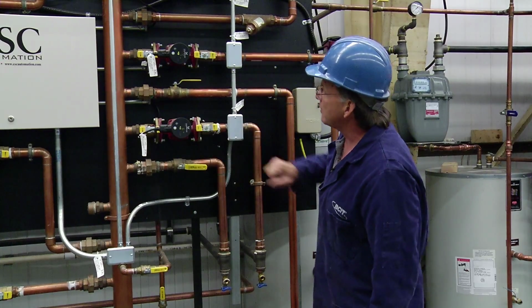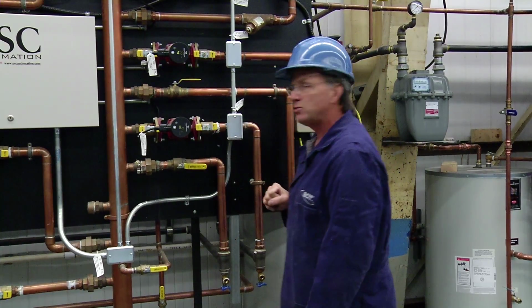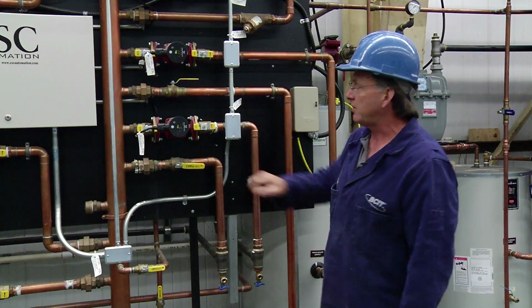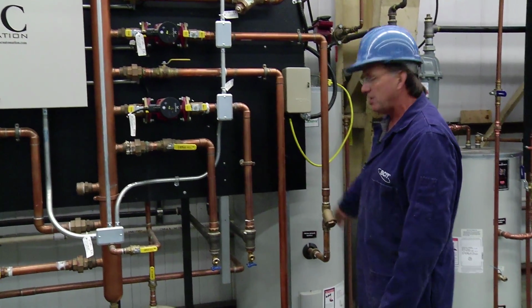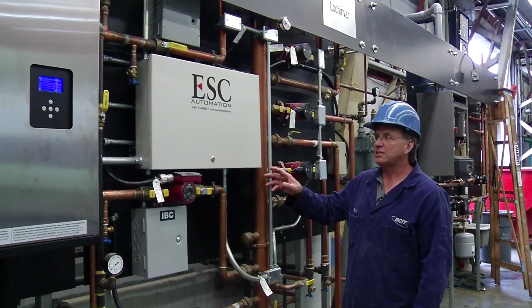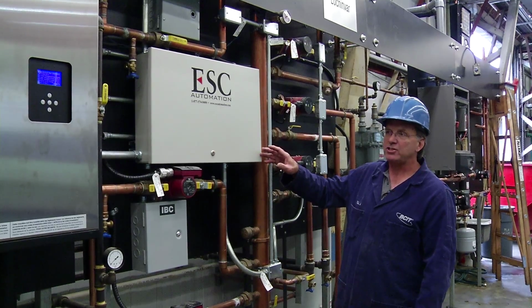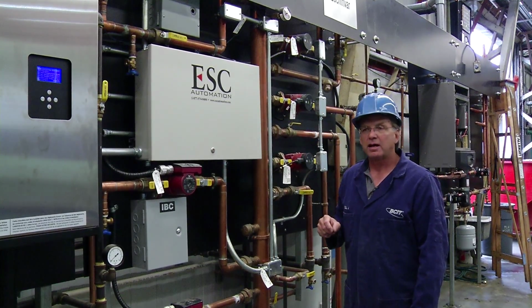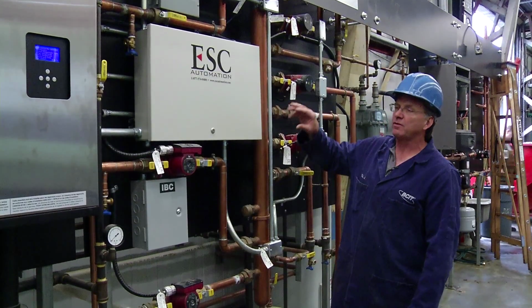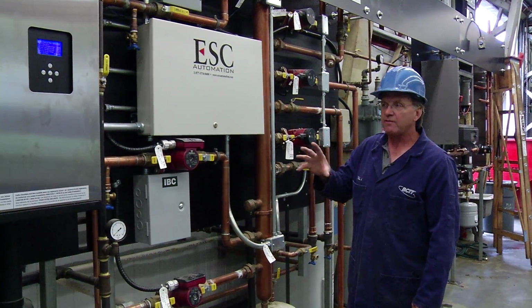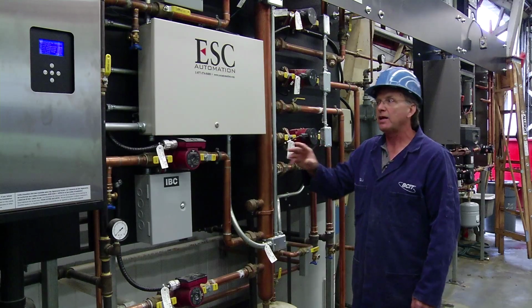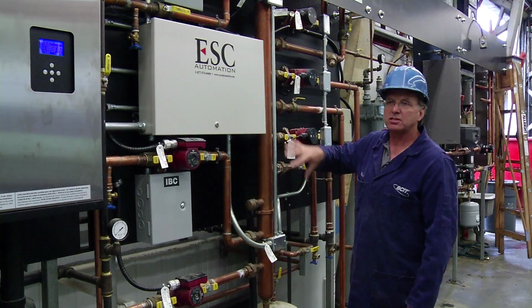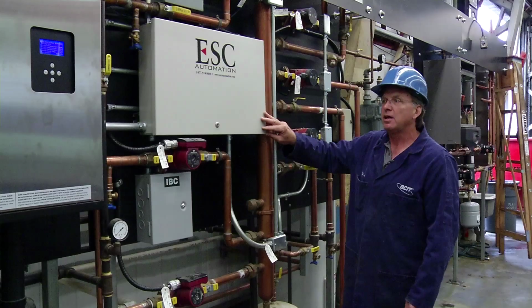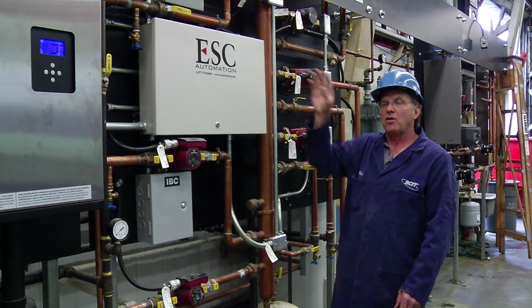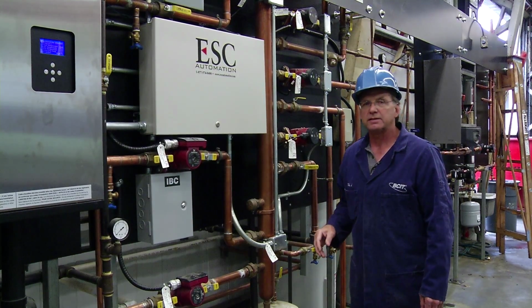And you can see right now that this one here is only going through about 6 watts of energy right now. It happens to be firing into the hot water tank. In this particular case, all the information from this operating and functioning system is fed back to our central heating boiler room at BCIT. The boilers themselves all have their own control systems in terms of firing, but all of this information of what this system is doing, what the set temperatures are and the cycling of the pumps, is going back to our central heat.